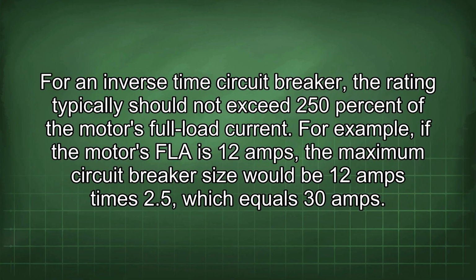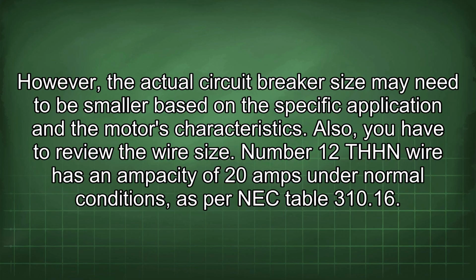For an inverse time circuit breaker, the rating typically should not exceed 250% of the motor's full load current. For example, if the motor's FLA is 12 amps, the maximum circuit breaker size would be 12 amps times 2.5, which equals 30 amps. However, the actual circuit breaker size may need to be smaller based on the specific application and the motor's characteristics. Also, you have to review the wire size.